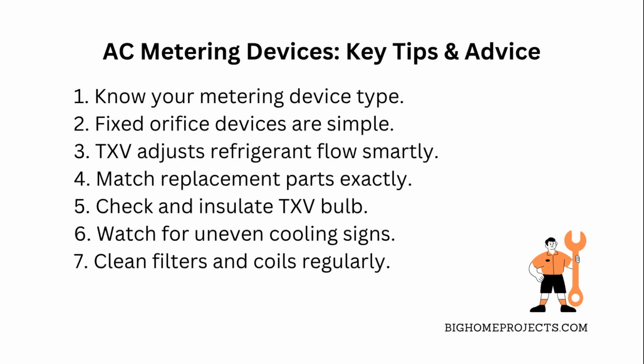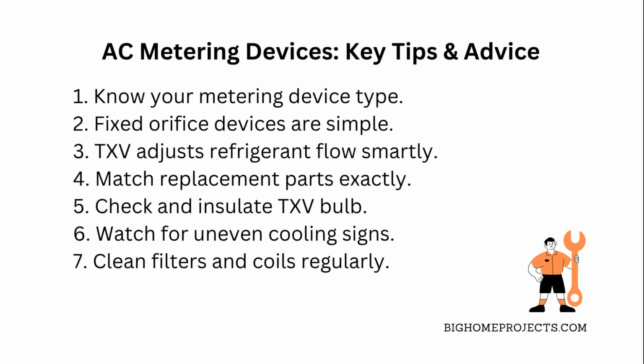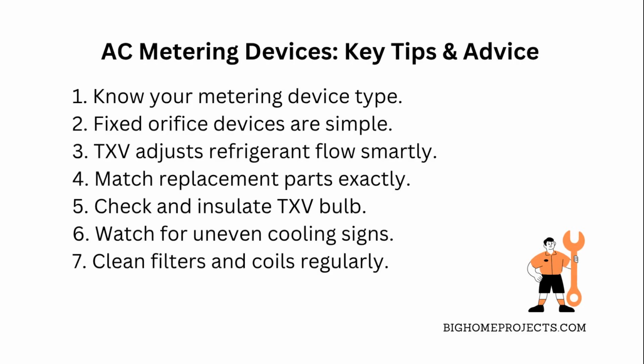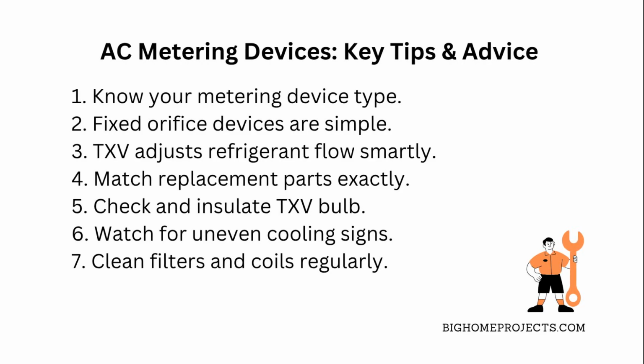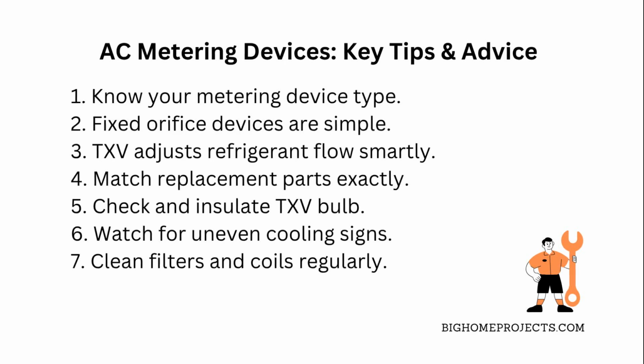When you're checking or replacing parts, always make sure you know which metering device your system uses, because swapping one for the other usually won't work right. Also, keeping an eye on the TXV's sensing bulb is key, since if it's not properly attached or insulated, your AC might freeze up or underperform.